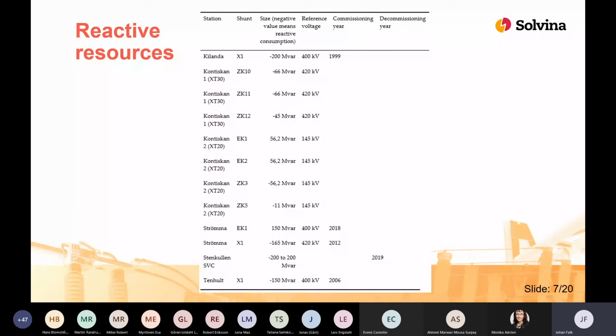There are both mechanically switched shunts and thyristor switched shunts in the area, namely the SVC in Stenkullen. Since the time period which we have studied is up to 2019, the situation isn't the same now. For instance, the SVC has now been decommissioned and will be replaced by a Statcom, also in Stenkullen.